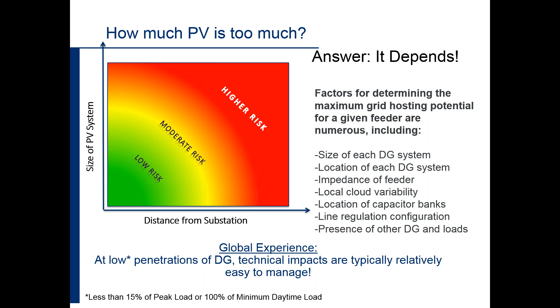In general, though, large systems that are distant from substations are more challenging than smaller, close systems. It's also really important to note that technical impacts are generally easy to manage at penetrations of less than 100% of minimum daytime load or less than 15% of total peak load.